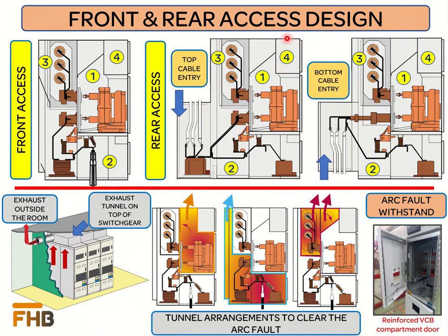The arc fault can occur within the switchgear despite little probability. An arc fault endangers operating and maintenance personnel as excessive light and heat is produced by an arc fault. Direct exposure to such heat radiation can cause severe burn injuries. The switchgear is designed in a manner that in case of an arc fault, it is contained within the switchgear with no harm to the operating and maintenance personnel. The switchgear compartments are fitted with tunnel arrangement to clear the arc fault outside the building to a safe space. Further, the VCB and cable compartment doors are fitted with special arrangements to make sure that these remain closed during the arc fault.